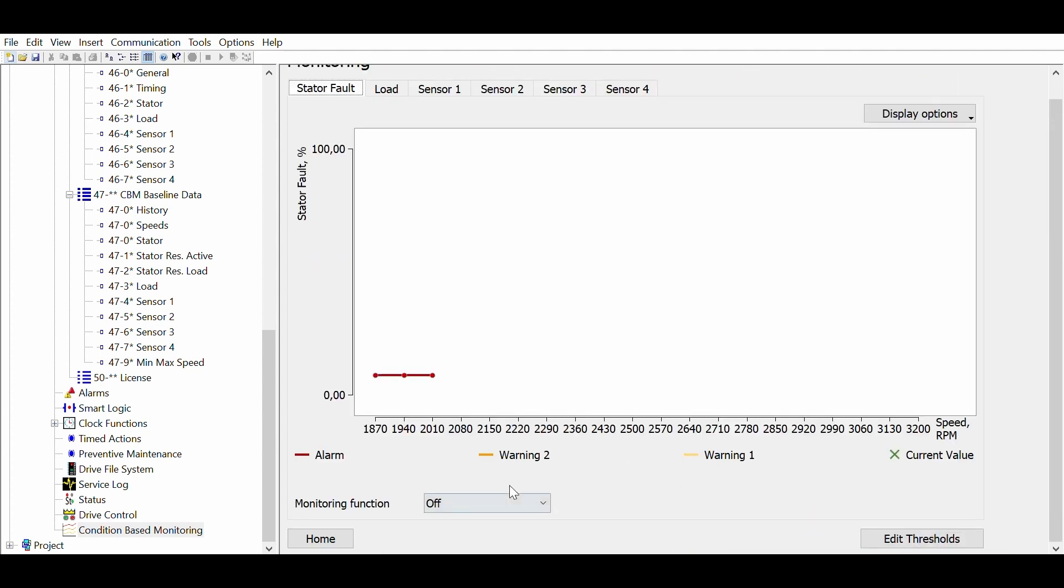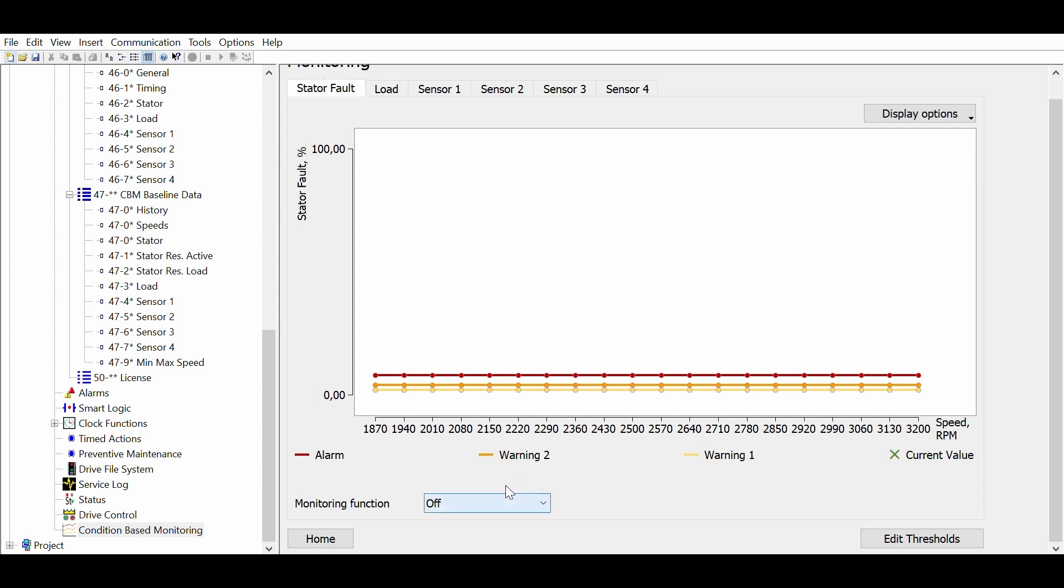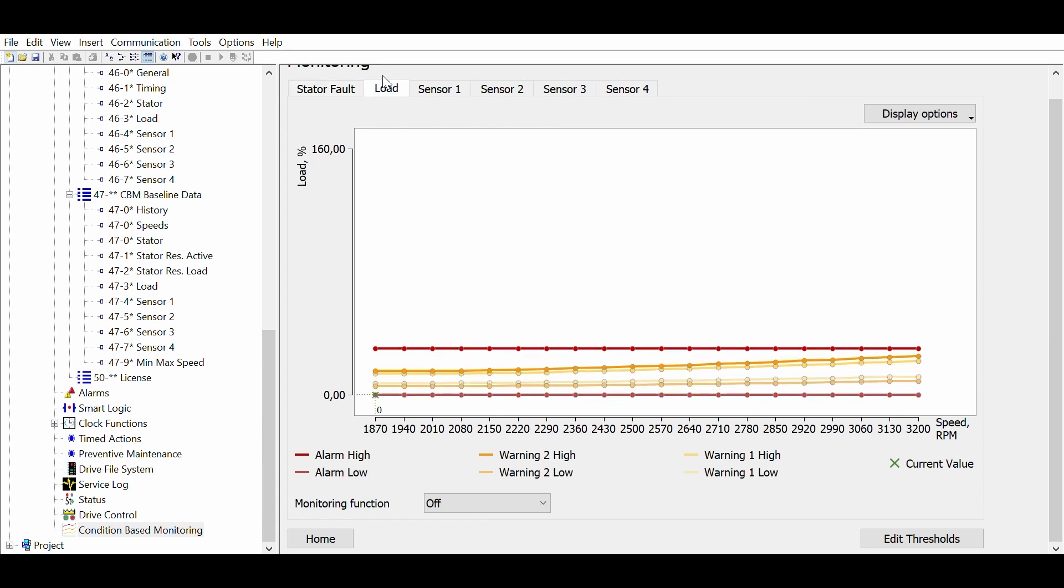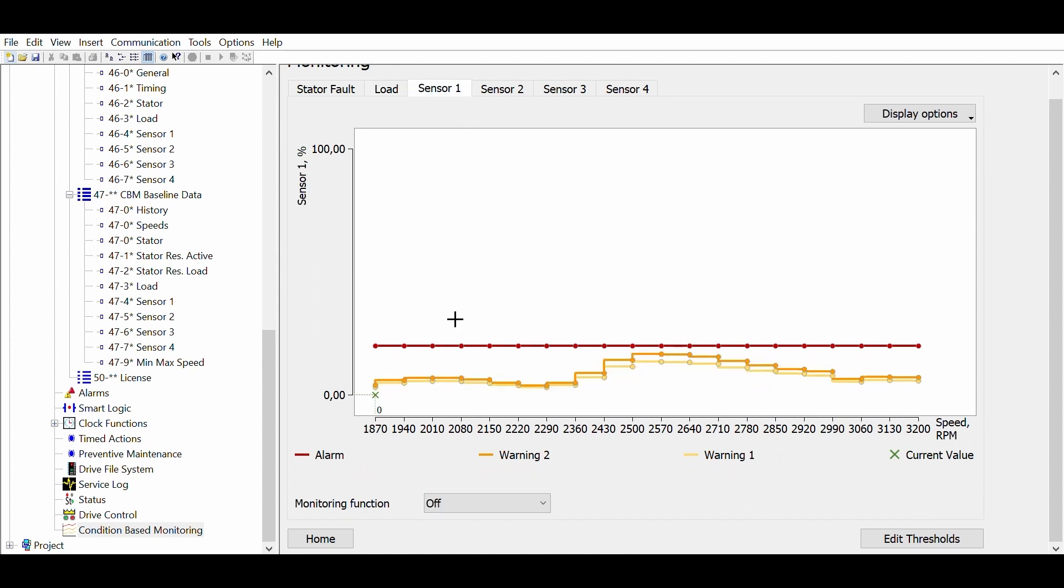You can now activate the monitoring. For each function you can choose whether you want to get only warnings or you also want to have the alarms. It is important to know that if an alarm is triggered, the drive will stop. In most cases only warnings are used.